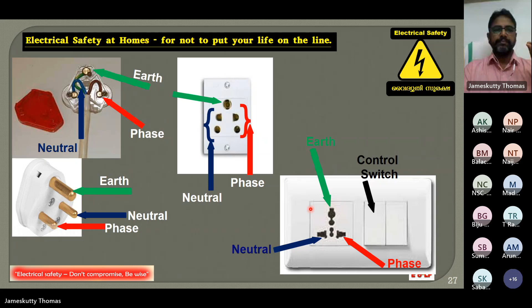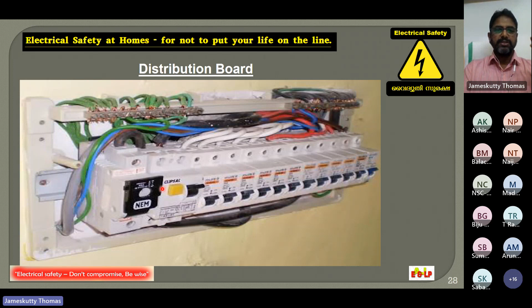These are sample DBs, distribution boards installed inside our house from where all the circuits are distributed. These are MCBs, and you can see one RCD or RCCB here. This is also another DB. Now earthing. Here the earth electrodes are shown. Actually, the earth electrodes are to be strictly done as per IS, Indian Standard 3043/2018. In some non-standard cases, simply a GI pipe will be inserted into the earth, which can cause accidents and will affect our electrical safety.